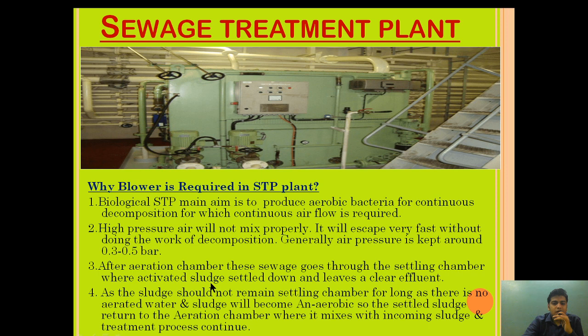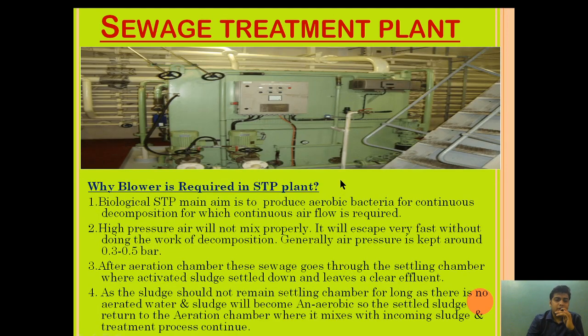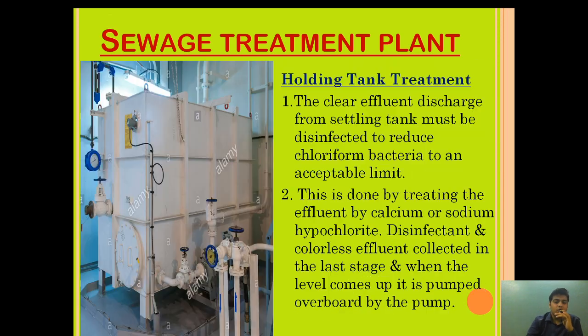After the aeration chamber, the sewage goes to the settling chamber, where the activated sludge settles down and leaves a clear effluent. The clear effluent passes to the disinfectant tank. The activated sludge must not remain settled in the settling chamber for too long, as there is no aerated water there and the sludge would become anaerobic. Therefore, the settled sludge is returned to the aeration chamber, where it mixes with incoming sewage and the treatment process continues.